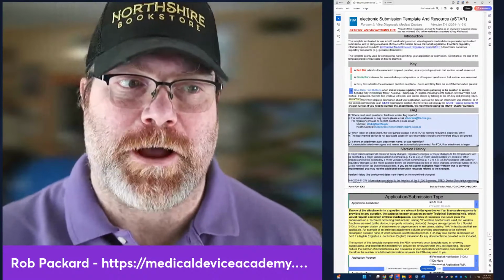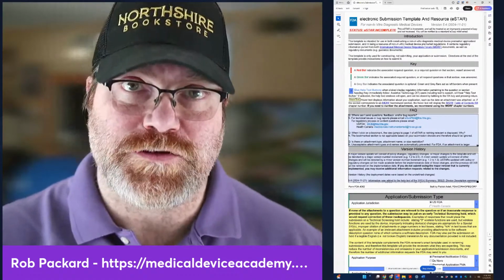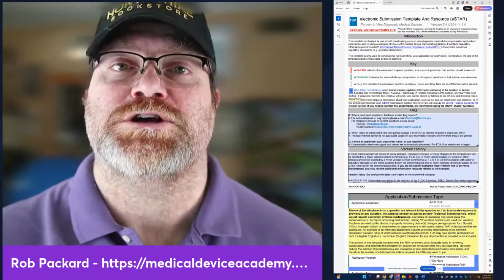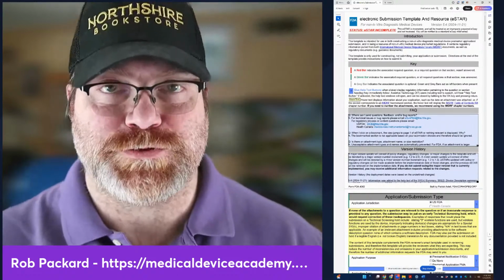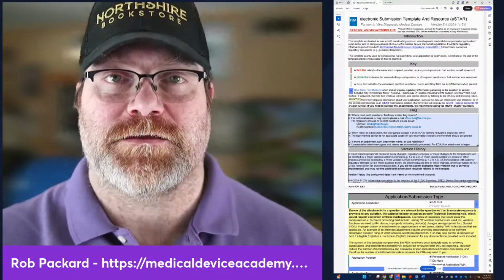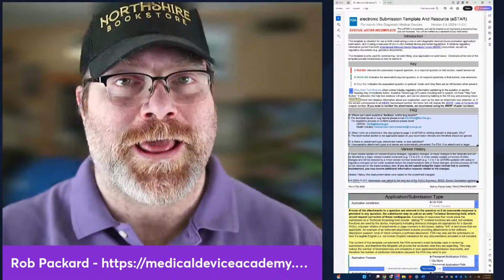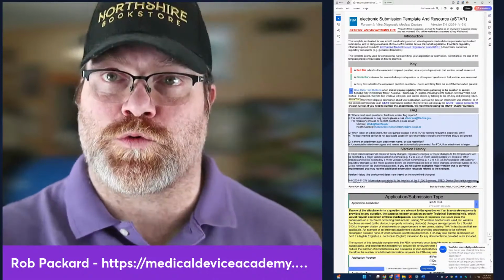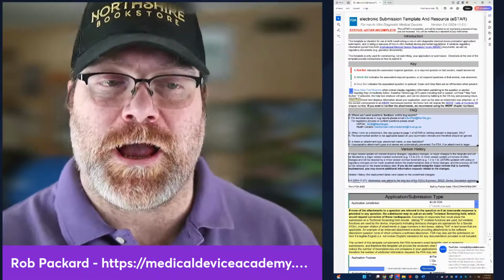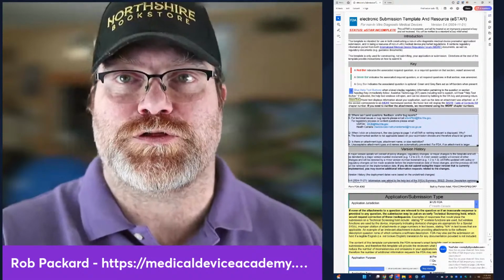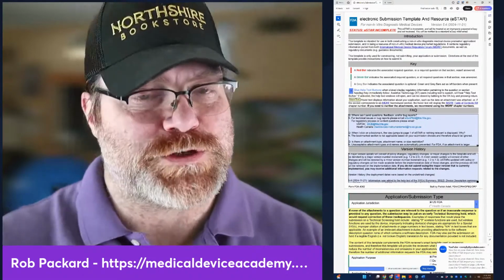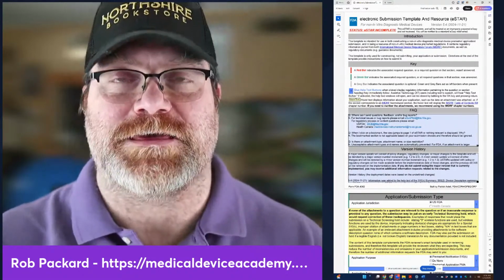Today, we're going to talk about how the FDA eSTAR template for 510Ks changed the device descriptions that you have to submit to the FDA. Now, first of all, you don't have to change anything that was working before. You could just say, I'm going to take exactly the template that I was using before for my device description. I'm just going to submit that as is.